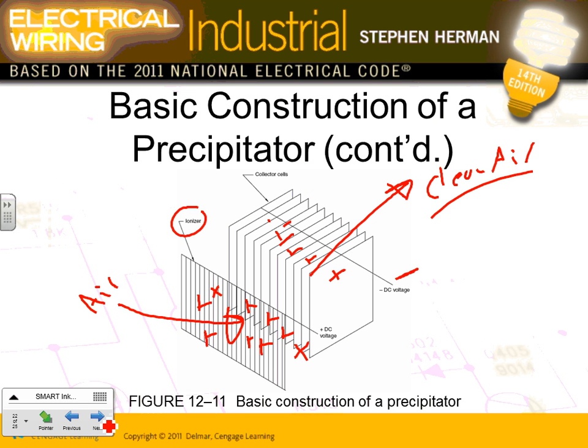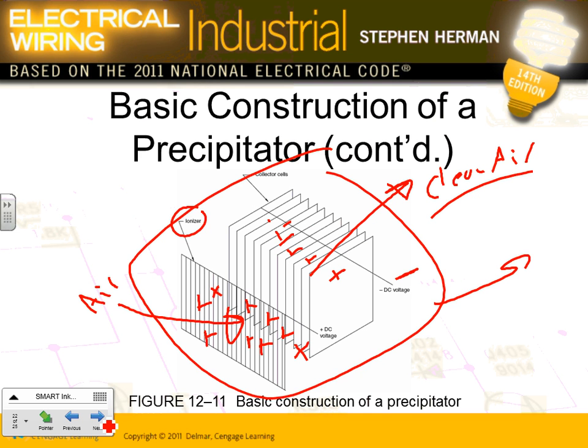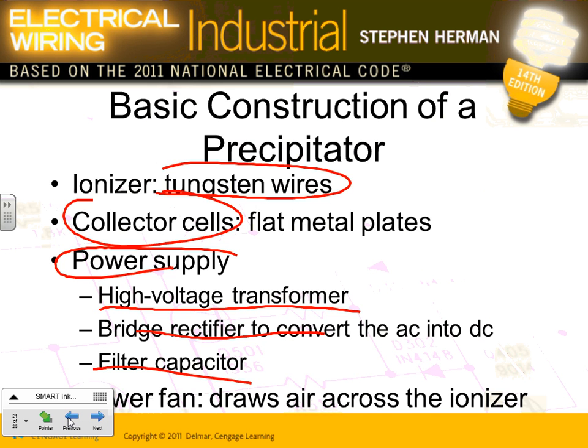Any comments, guys, about this precipitator? So what's your job, Darren? Your job is to size the overcurrent protection device and feeder. How do you size this system, guys? Based on recommendation from manufacturers, definitely. What size do they want? They will tell you the overcurrent protection device as well as the feeder. We can do some calculation.